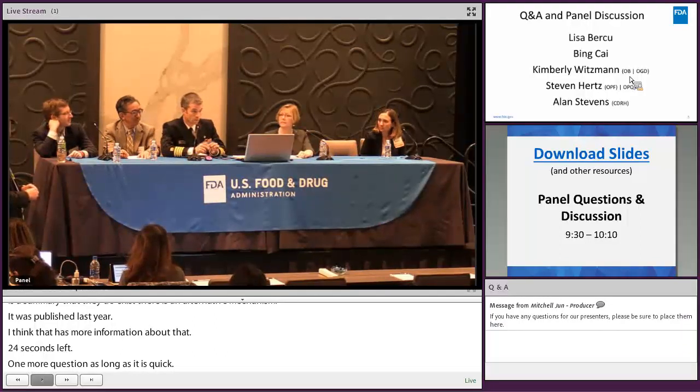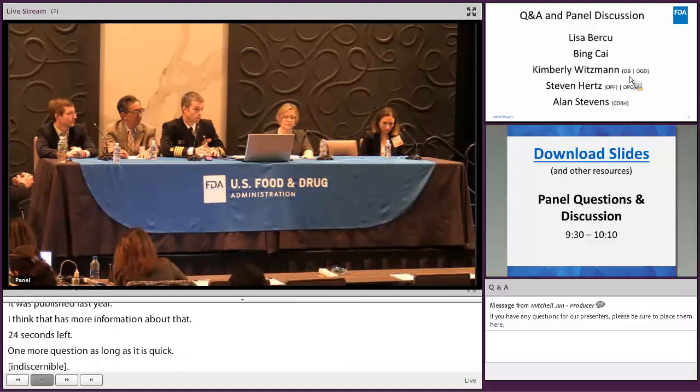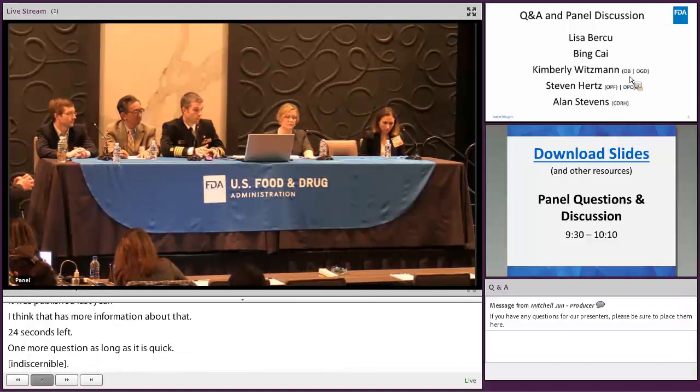So I think, from the CDER point of view, when you're talking about design controls for a combination product, generic combination product, you're still responsible for documenting what the design inputs and outputs are for your product, how you verified and validated that your product is meeting its requirements.